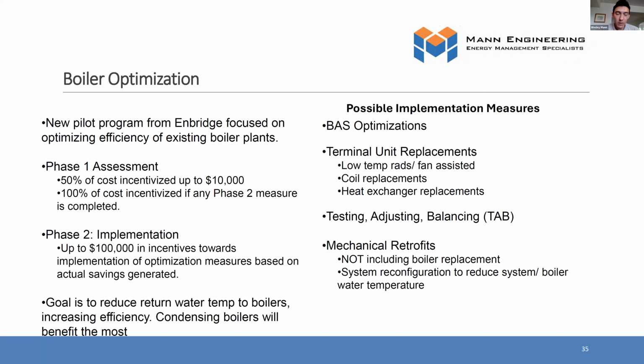So one important thing to know about condensing boilers that I like to tell all my clients is that the nameplate efficiency is only achieved at certain operating conditions, meaning that you actually need to have very low water temperature going into the boiler. Now, the thing about most existing buildings, they were designed around non-condensing boilers, which require the water temperature going into the boiler above 130 degrees. So when you're retrofitting a condensing boiler into a boiler system that was designed to work with non-condensing boilers, it will never condense, and you will basically get the same efficiency as you would get with a non-condensing boiler.